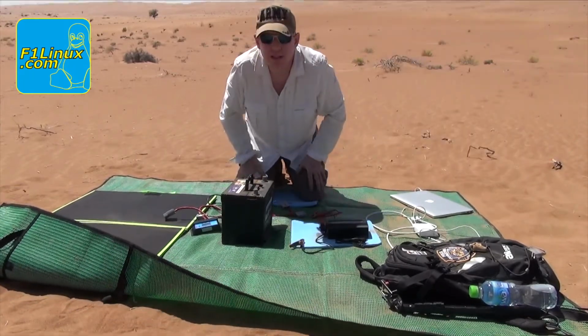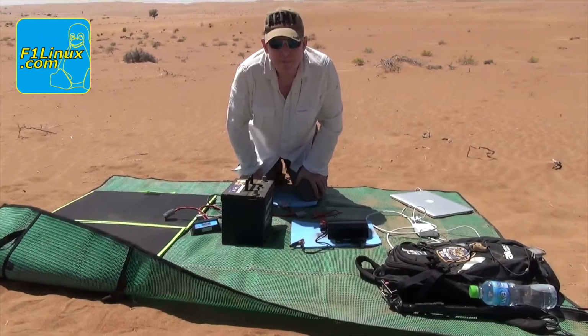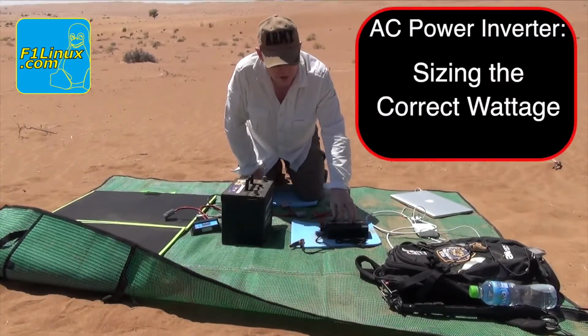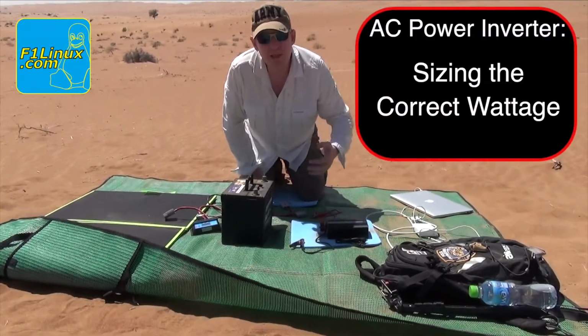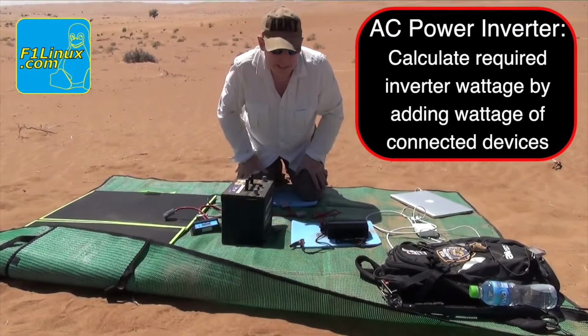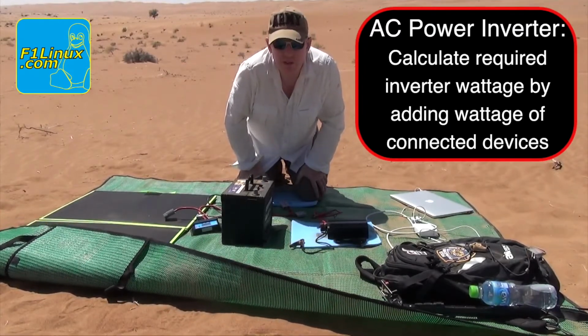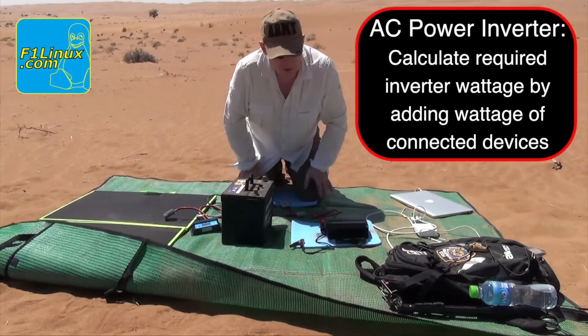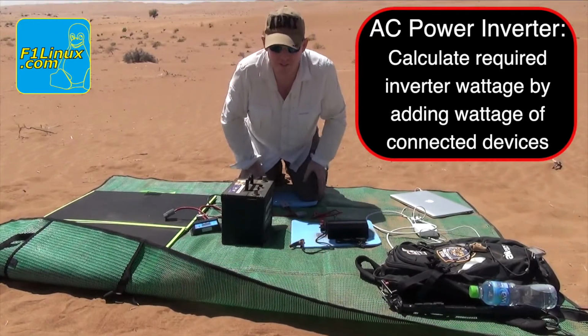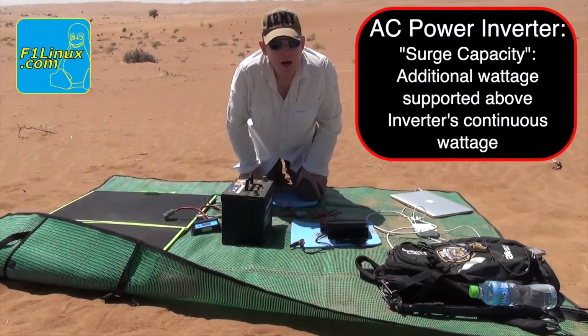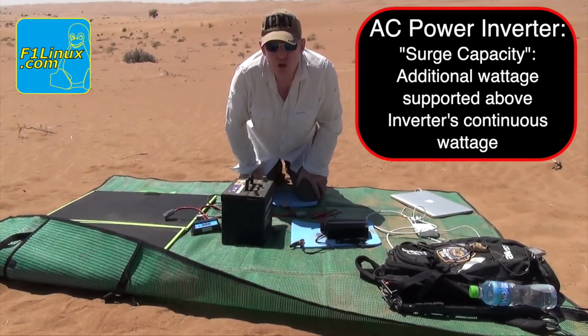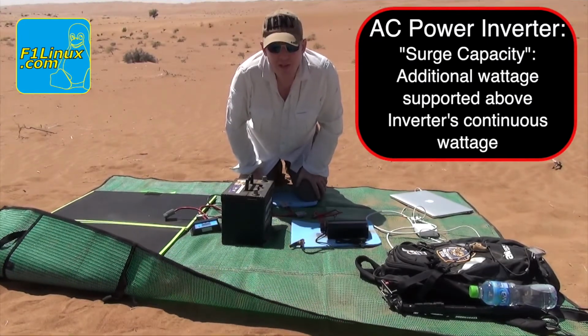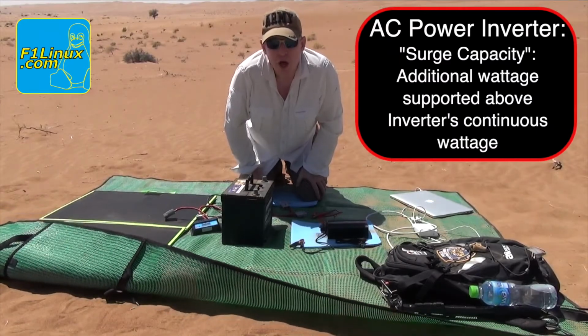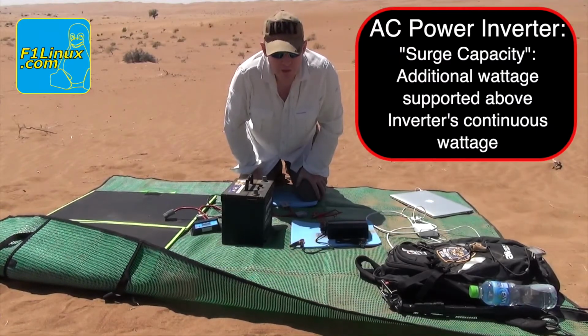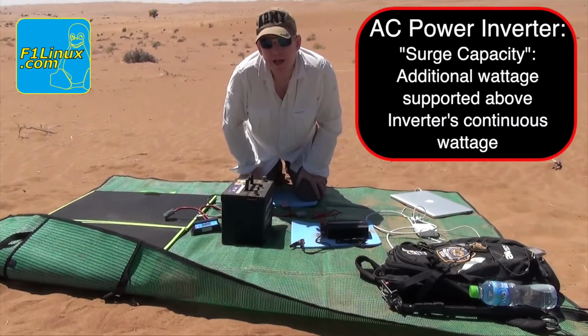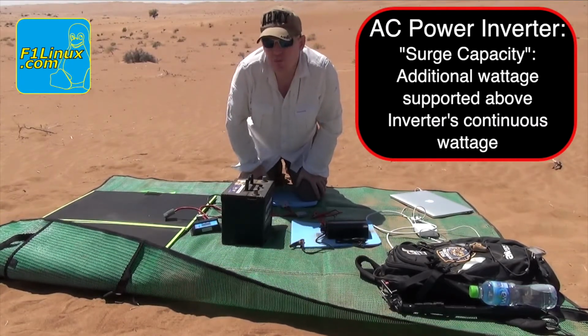Another thing you have to look at is the surge capacity. In sizing an inverter in terms of wattage, you merely add together all the watts of the devices, and hopefully it'll be less than the size of the inverter you're hoping to buy. Some devices, like things with motors, will have a greater initial requirement than what they continuously run at.